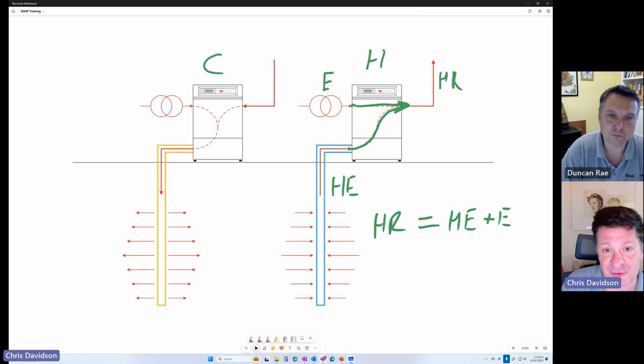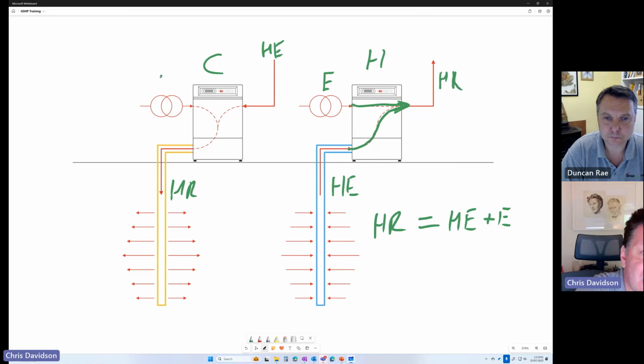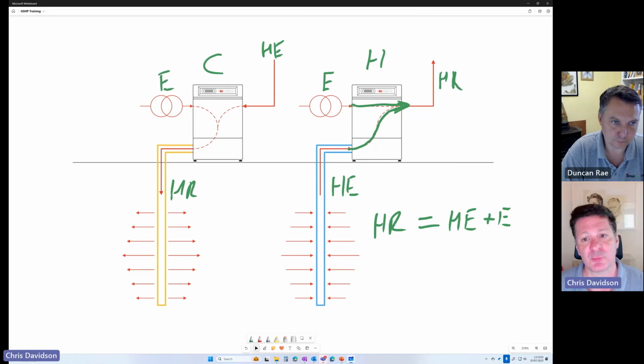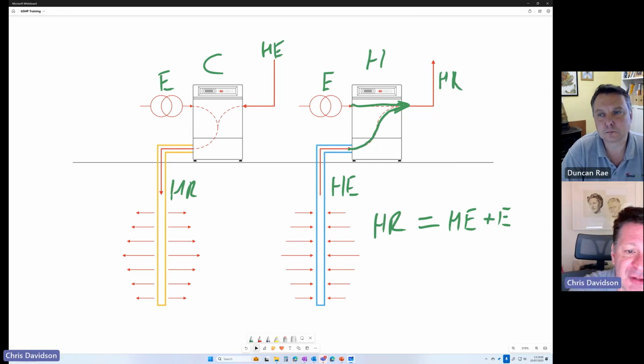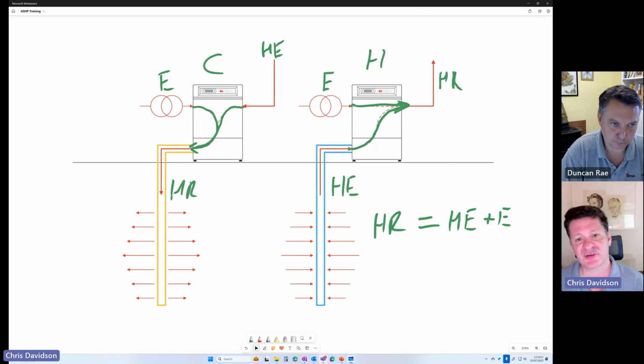In cooling mode, now things are reversed. So our heat being extracted is being extracted from the building, and our heat being rejected is into the ground. And again, we have our electrical consumption to consider. And again, through the forces of friction, that electrical energy is added to the heat that's being taken, this time from the building, and this time it's being put into the ground. So whilst the processes of heating and cooling are similar, they're not identical because of the difference in where that electrical energy ends up as heat in the system.